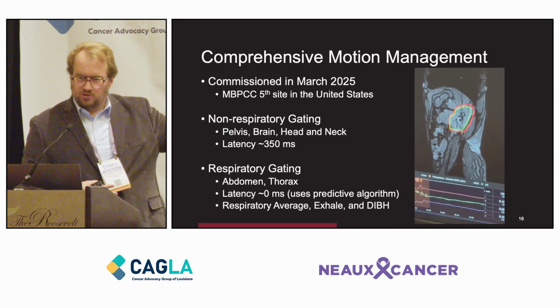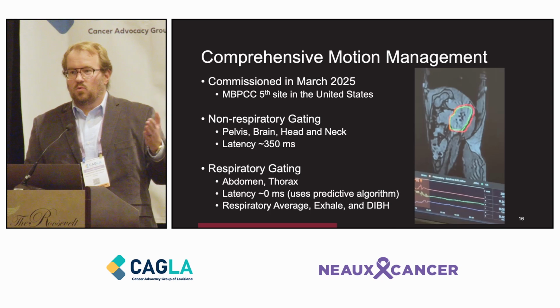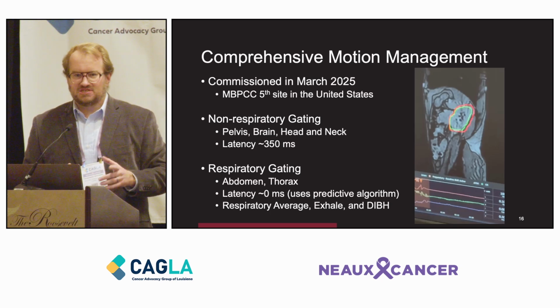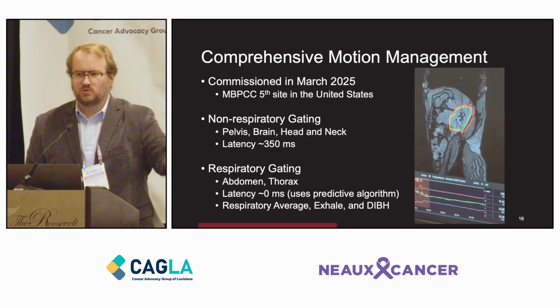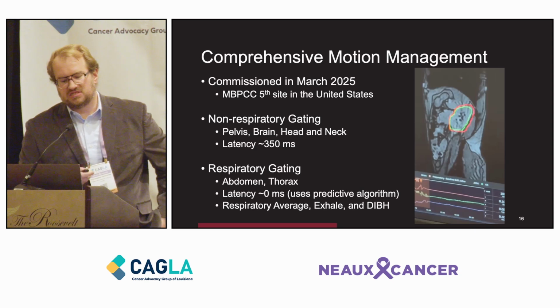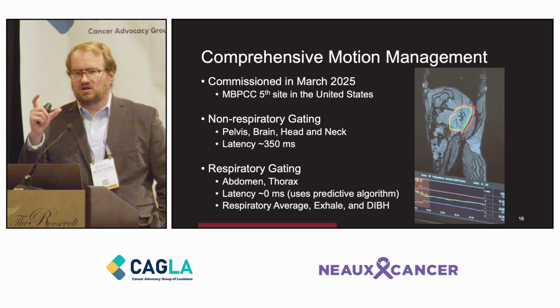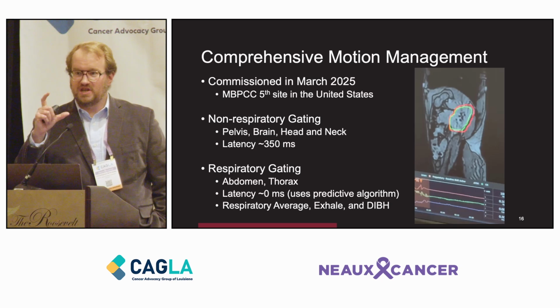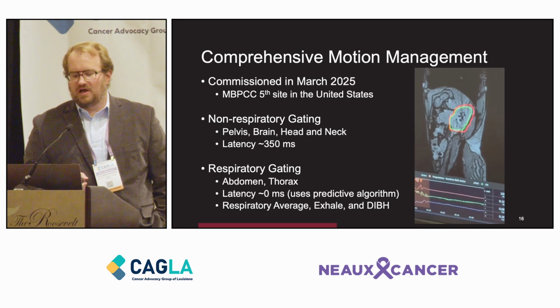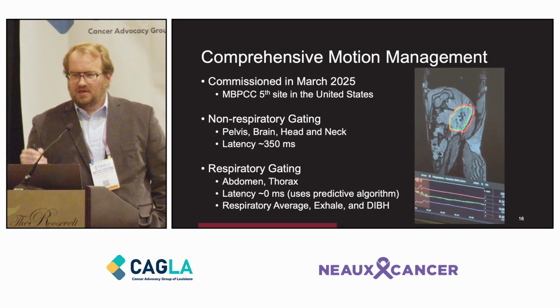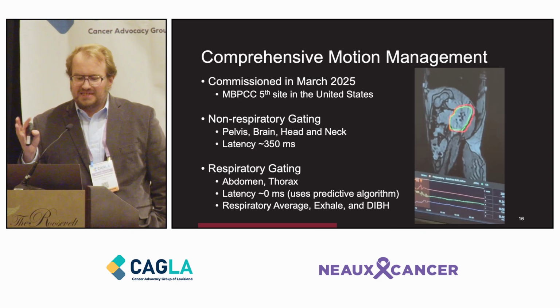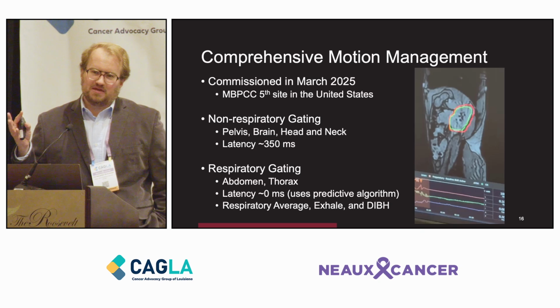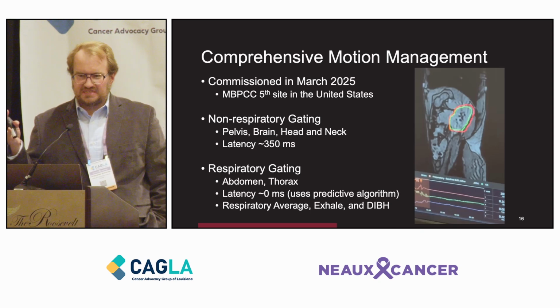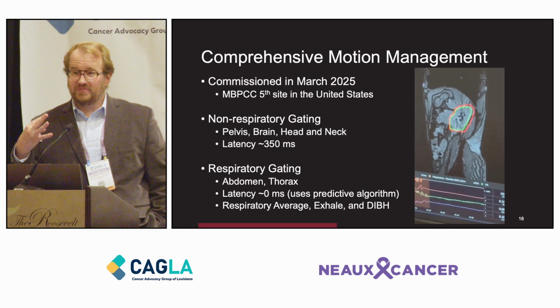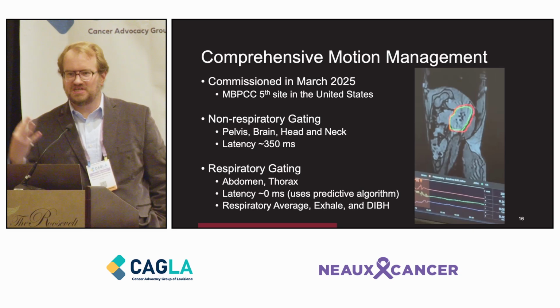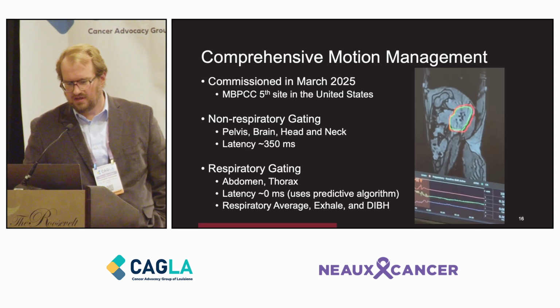Prior to this tumor tracking upgrade, we would have relied on our radiation therapists to see this on that motion scan and manually pause the beam. But with this upgrade, if the system detects that any part of the target moves outside of that defined, acceptable window, it will automatically hold the beam. There is a little bit of latency in the imaging, so it might take about 300 milliseconds for this to kick in and hold the beam, but that's certainly much faster than the human reaction time of seeing a change, reaching out and pressing a button.